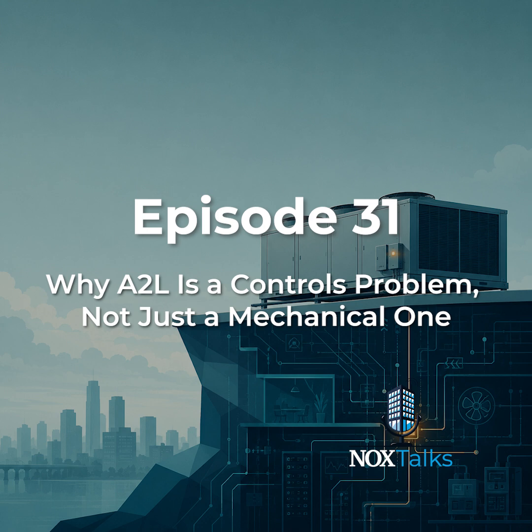There are real standards behind this. ASHRAE Standard 15 on refrigeration safety and product standards like UL 60335-2-40 for heat pumps and air conditioning equipment, which drive when leak detection and mitigation are required. The takeaway: your mechanical contractor and your controls contractor both need to be in the room, and on a lot of projects, they're just not.